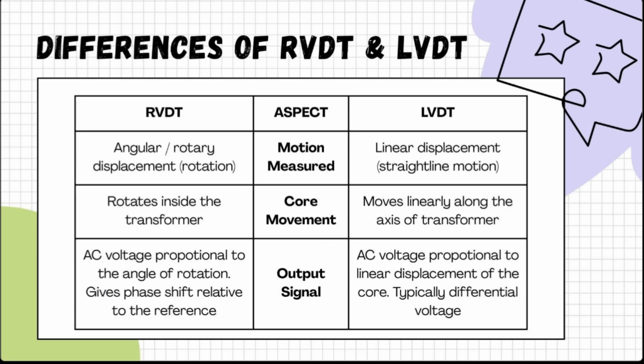Now, we look at how different RVDT is to its counterpart, Linear Variable Differential Transformer, or LVDT. Firstly, RVDT measures angular displacement, while LVDT measures linear displacement, since the core in RVDT rotates inside the transformer, while the core in LVDT moves linearly along the transformer's axis.